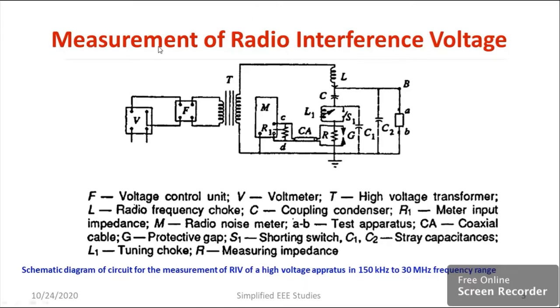This is the basic setup for measuring radio interference. The heart of the component is the radio interference meter. One more important information: you can measure the signal in the range of 150 kilohertz to 30 megahertz. Above and below this limit you cannot measure — that is the peculiarity of this meter. By using this setup we can measure the radio interference and check whether it is beyond the limit or within the acceptable level.